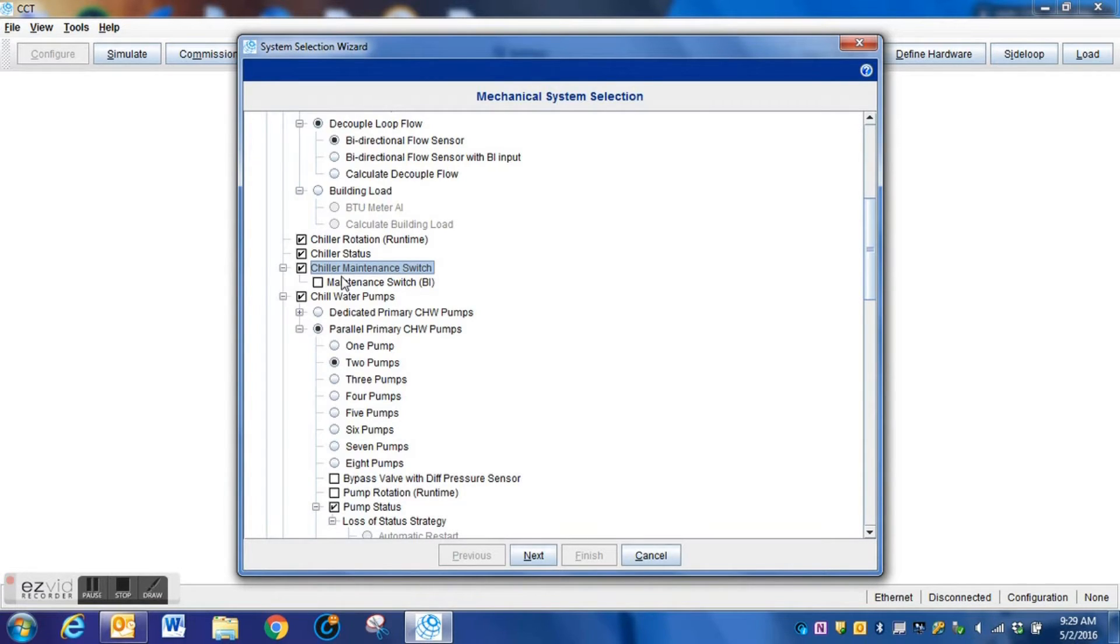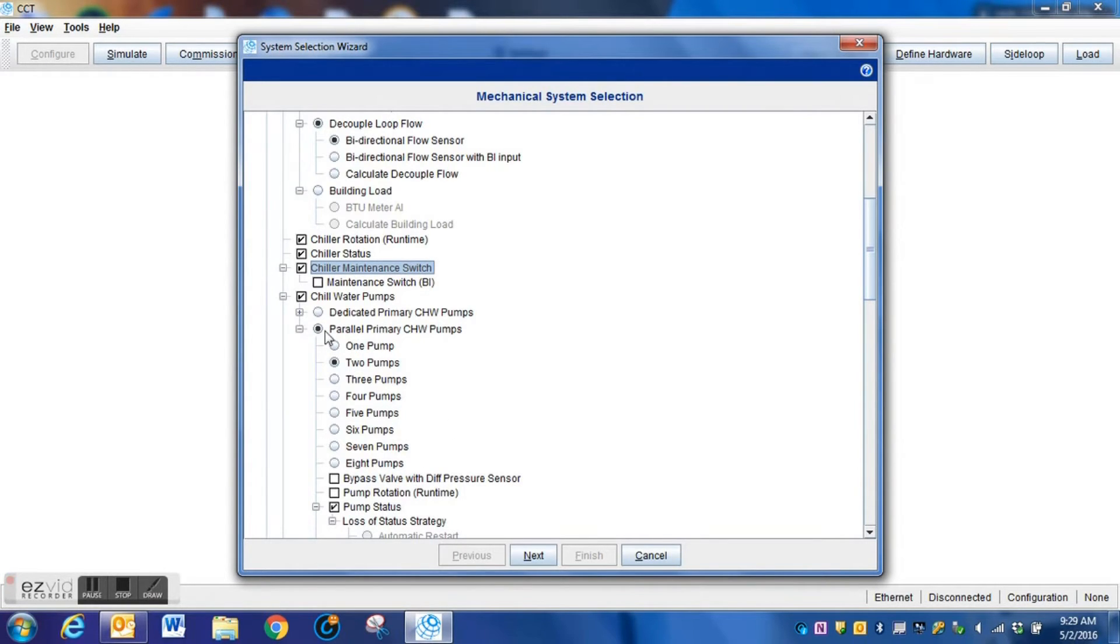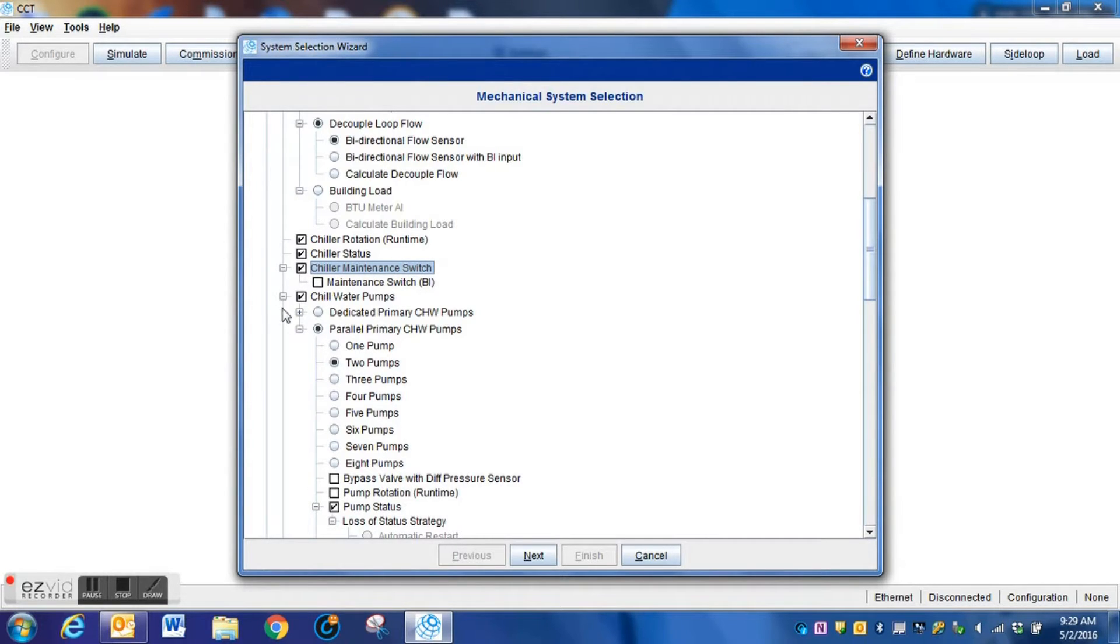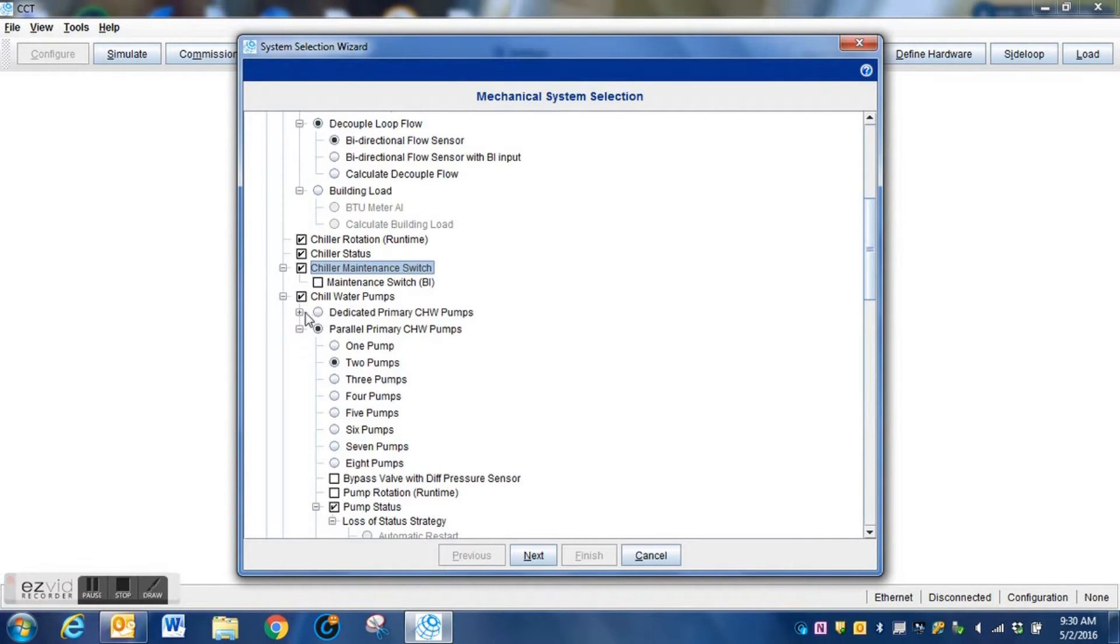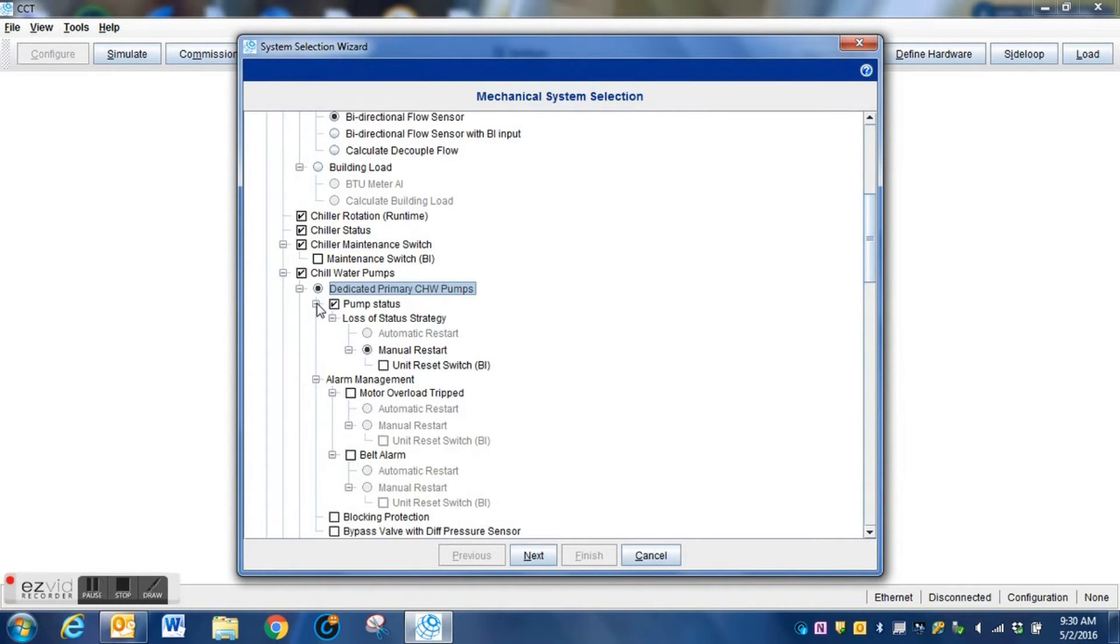Some things that you will need to know is whether or not the pumps are dedicated to a particular chiller. Some mechanical configurations in chilled water systems require that a specific pump runs with a specific chiller. Others have some redundancy where either pump can run with either chiller. Those are questions you're going to need to know the answers to.